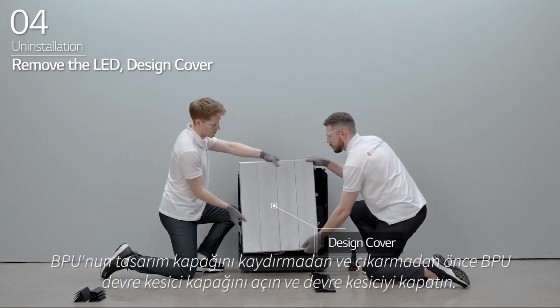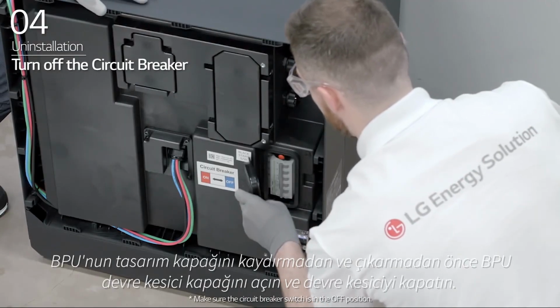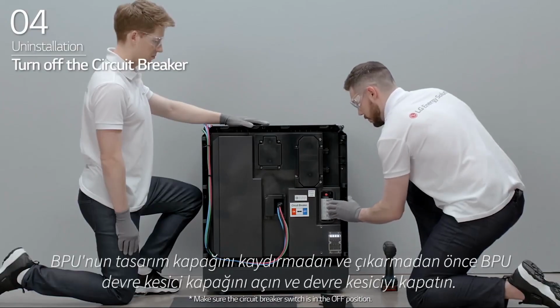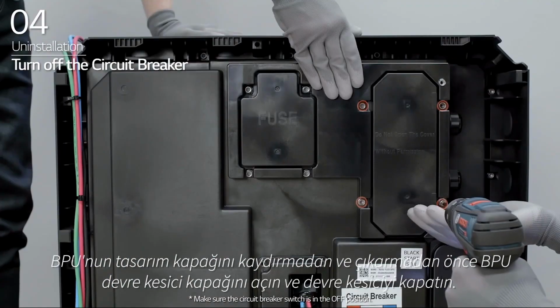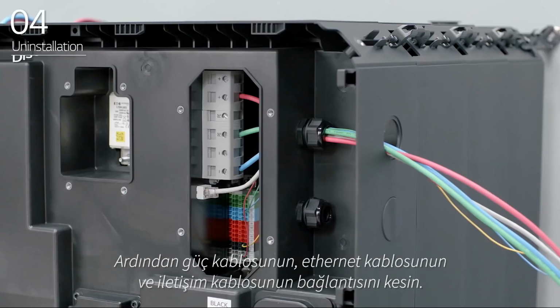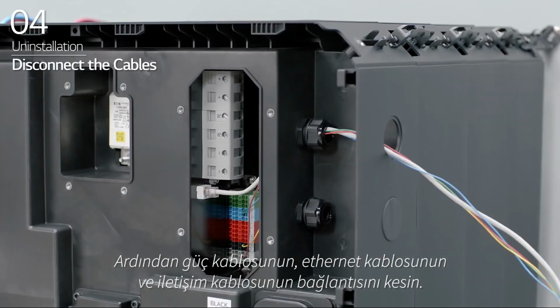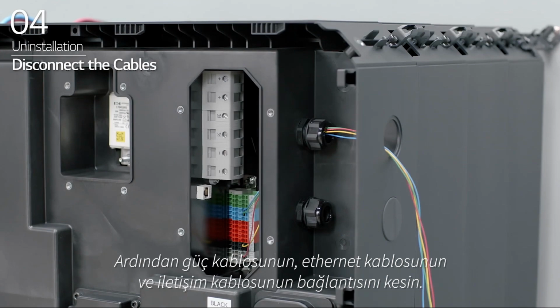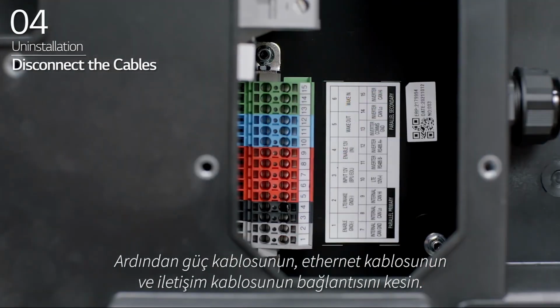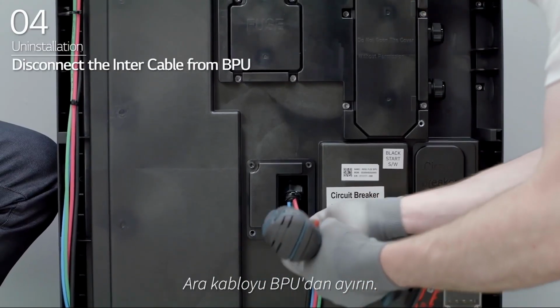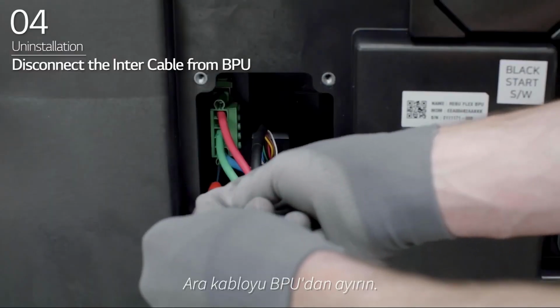Before sliding and removing the design cover of the BPU, open the BPU circuit breaker cover and turn off the circuit breaker. Then, disconnect the power cable, the Ethernet cable, and the communication cable. Disconnect the intercable from the BPU.